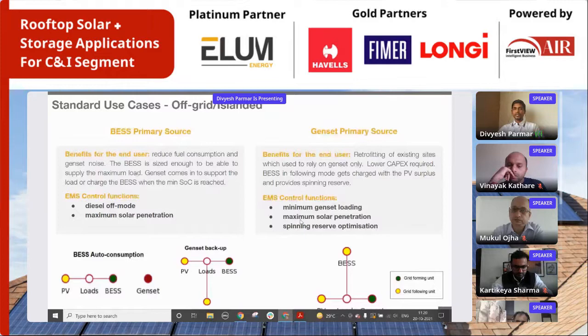Here our controller functions with EMS features like minimum genset loading, maximum solar penetration, and operation reserves. The second application is for greenfield projects, like BESS as the primary source, where you select a big size battery to form the grid, sufficiently sized to take care of the maximum load.